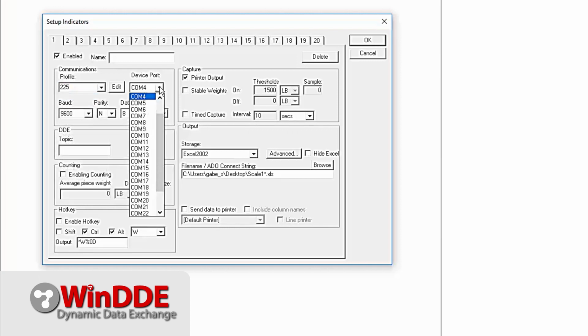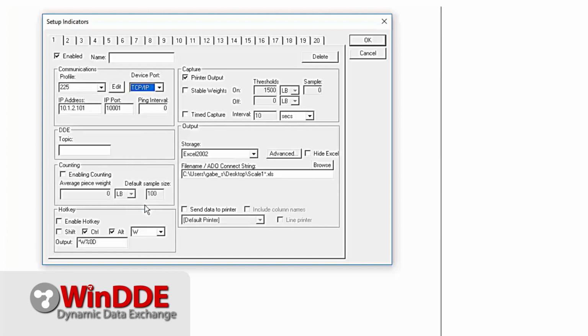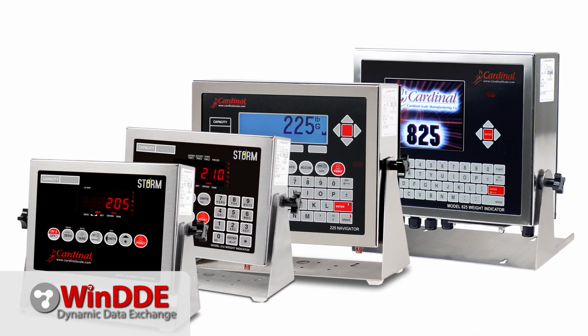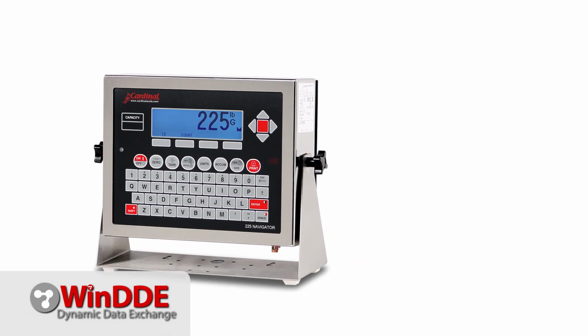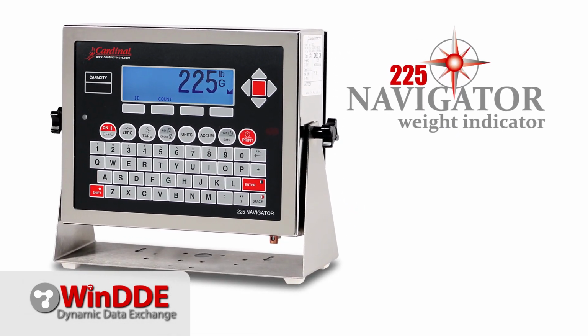Next, you will want to choose the device port, which is the connection type on the PC being connected to the weight indicator. If you are using TCP/IP, please make sure you use the IP address of the S2E1 and IP port 10001. WinDDE works with many different models of Cardinal Scale weight indicators, and in this video, we will show it connected to a Cardinal 225 Navigator indicator.